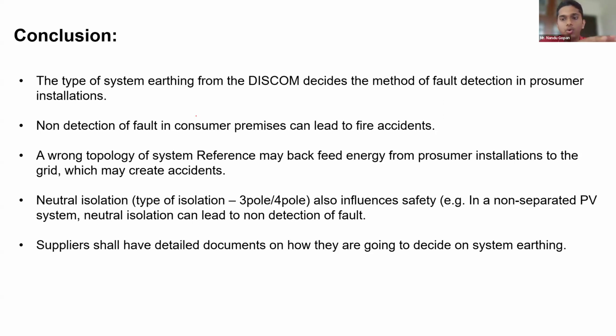So the main issue is with the discoms. What I've written here is, if the discom supplies as per regulations a TNCS supply, TNCS with PME, meaning there is an earth electrode in your installation, then most of your issues with respect to prosumer installations will be solved. But in most areas, they have supplied a TT. So if they supply a TT system, then if you want to change from a consumer to a prosumer, it can be really complicated.